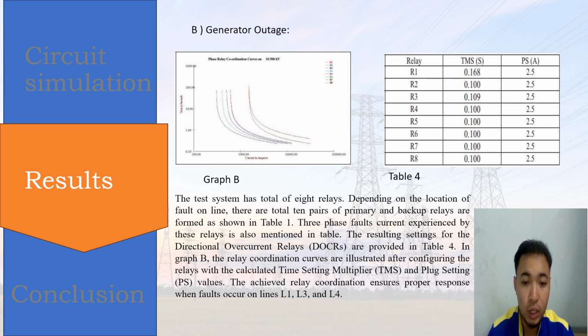In graph B, the relay coordination curve illustrates the result after configuring the relays with the calculated time setting multiplier and plug setting value. The achieved relay coordination ensures proper response when a fault occurs on line 1, line 3, and line 4.